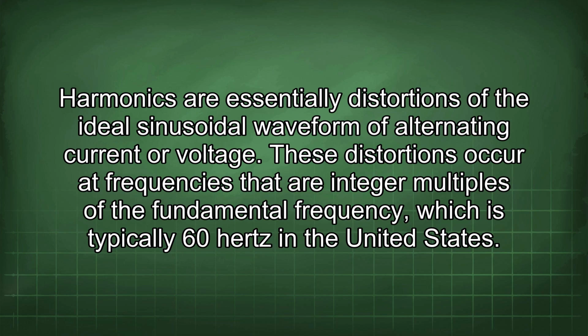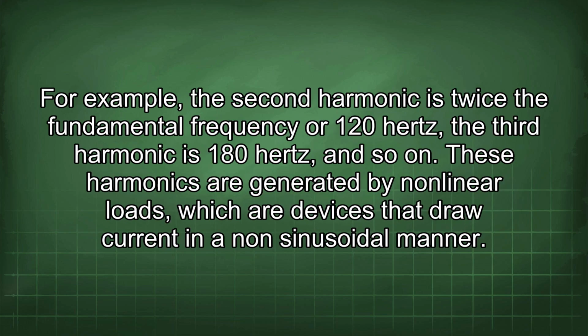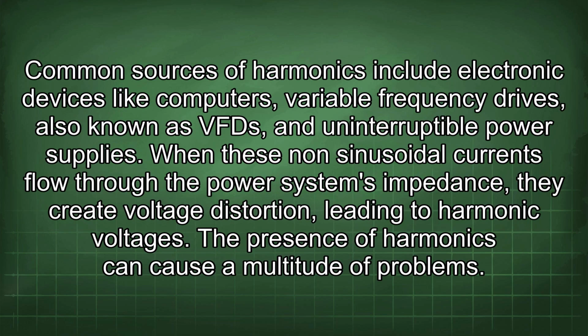Harmonics are essentially distortions of the ideal sinusoidal waveform of alternating current or voltage. These distortions occur at frequencies that are integer multiples of the fundamental frequency, which is typically 60 Hz in the United States. For example, the second harmonic is twice the fundamental frequency, or 120 Hz. The third harmonic is 180 Hz, and so on. These harmonics are generated by nonlinear loads, which are devices that draw current in a non-sinusoidal manner. Common sources of harmonics include electronic devices like computers, variable frequency drives, also known as VFD, and uninterruptible power supplies. When these non-sinusoidal currents flow through the power system's impedance, they create voltage distortion, leading to harmonic voltages.